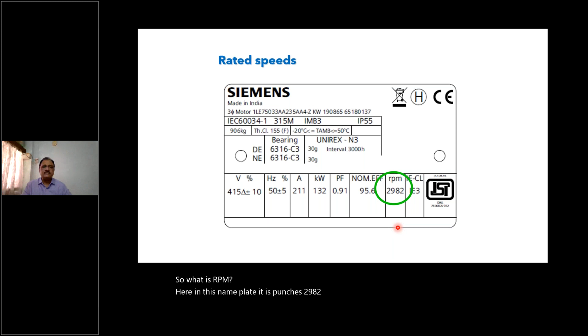The pole numbers, as you all know, 120 F by P will give you the synchronous speed. For a 2-pole 50 cycles, the synchronous speed 120 into 50 divided by 2 is 3000. For 4-pole it is 1500, 6-pole is 1000, 8-pole is 750, and 10-pole is 600. You will not find 10-pole motors being offered by many manufacturers because these are very difficult to manufacture, and only under specific inquiries are they manufactured and given.